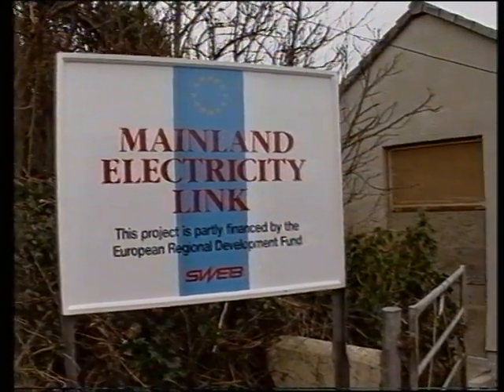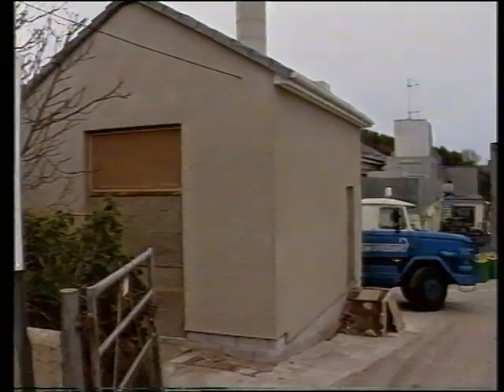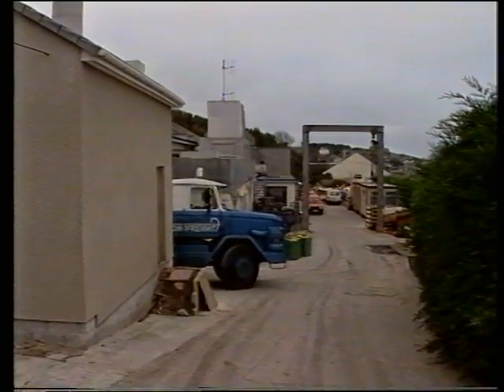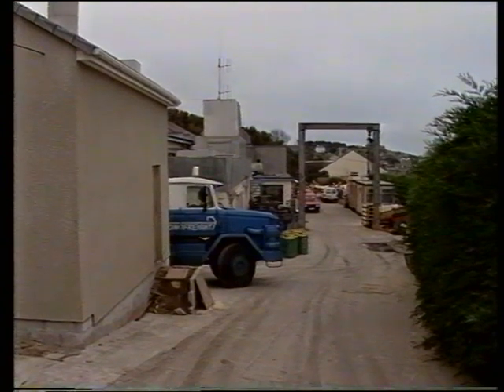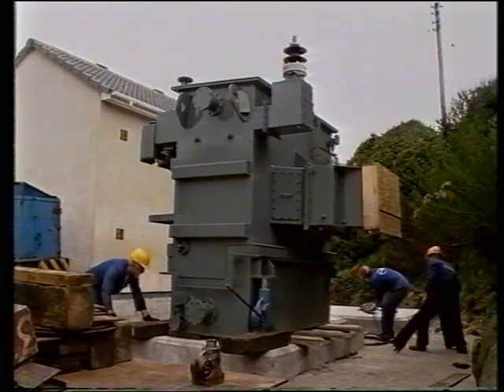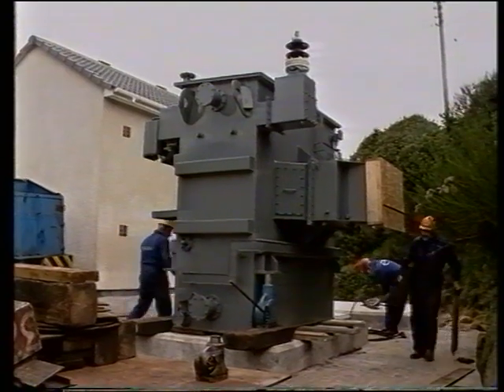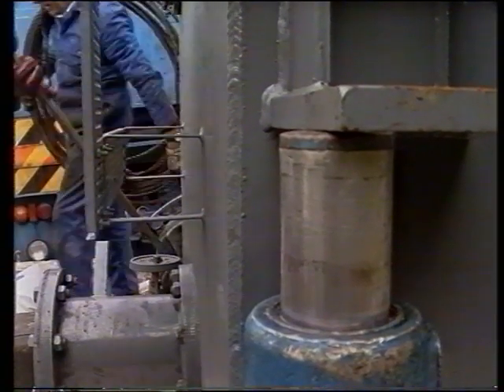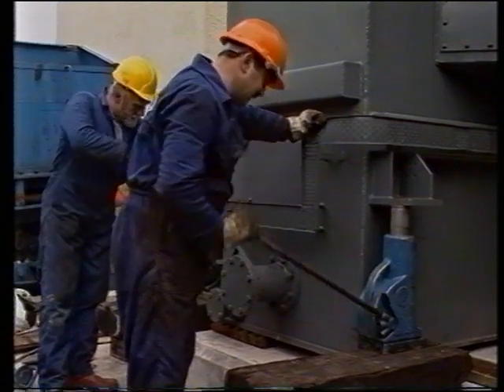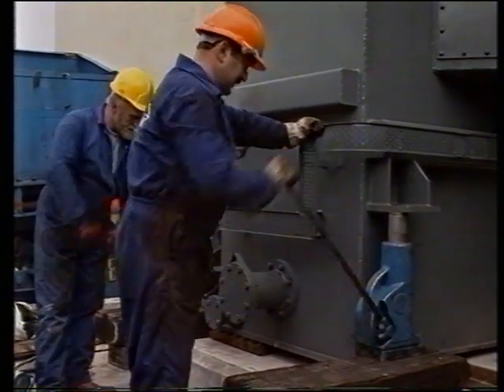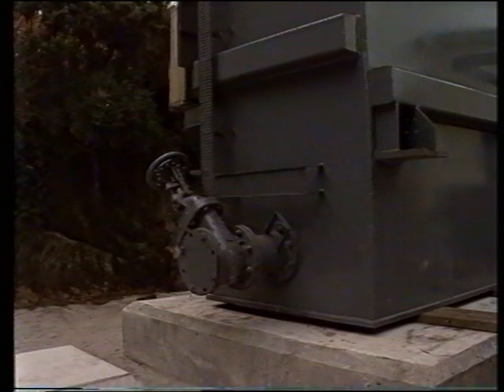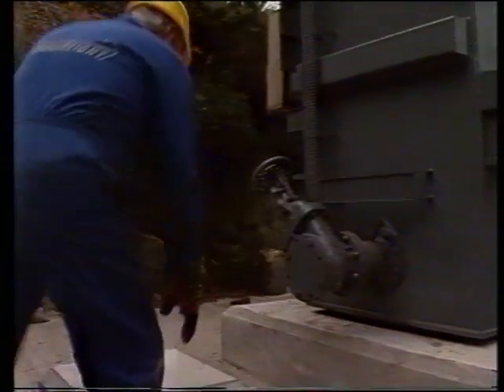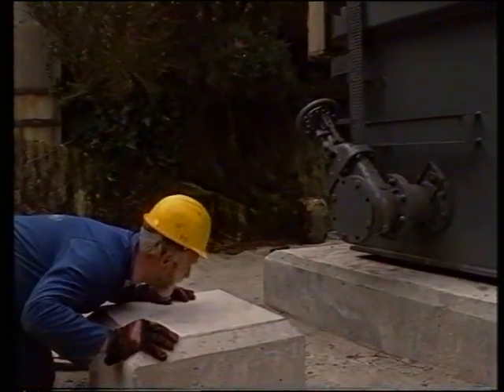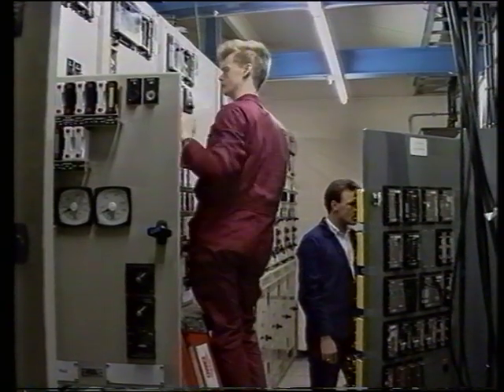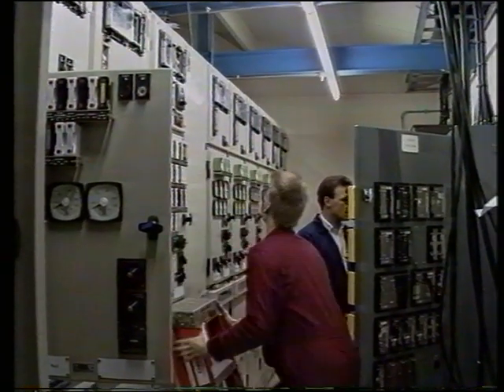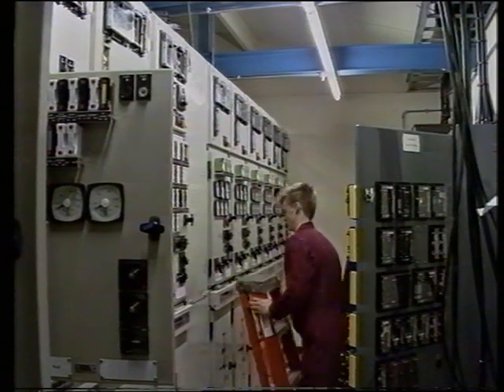A generous grant provided by the European Regional Development Fund covered half the total cost of the scheme, including a new transformer for SWEB's generating station brought over by landing craft from Penzance. The 33,000-volt supply will terminate at the transformer, where it'll be converted to 11,000 volts, ready for distribution around the islands. As well as the transformer, a 33,000-volt switch and new cooling tanks will be installed, and inside, space has been found for a new 11,000-volt switchboard.